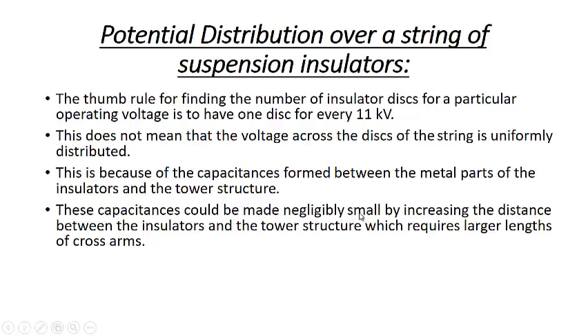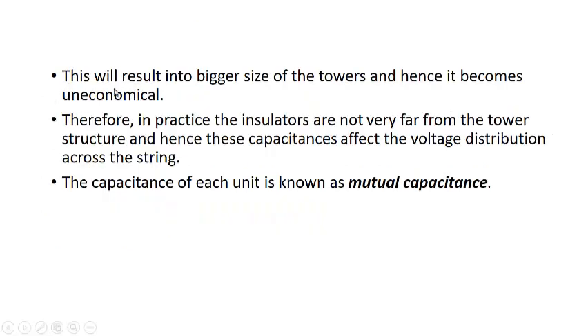These capacitances could be made negligibly small by increasing the distance between the insulator and the tower structure, which requires a larger length of cross arm. So we would have designed the towers in such a way that these capacitances are neglected by increasing the cross arm. But practically, if we do that, it results in the increase in the tower width, which increases the cost. So it's not done practically. This will result in the bigger size of the towers, and hence it becomes uneconomical. Therefore, in practice, the insulators are not very far from the tower structure, and hence these capacitances affect the voltage distribution across the string. So we need to see other methods which can be used to decrease this non-uniform voltage distribution.